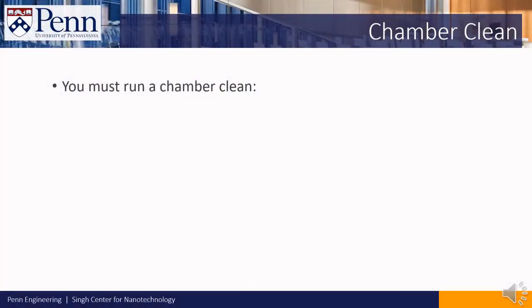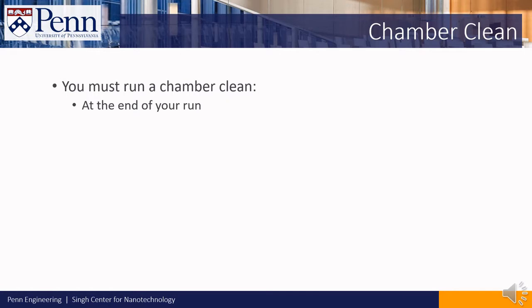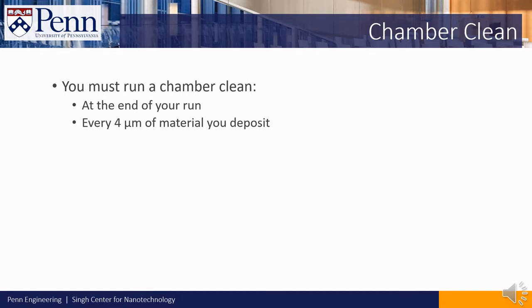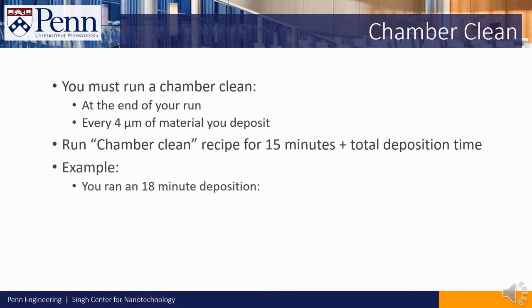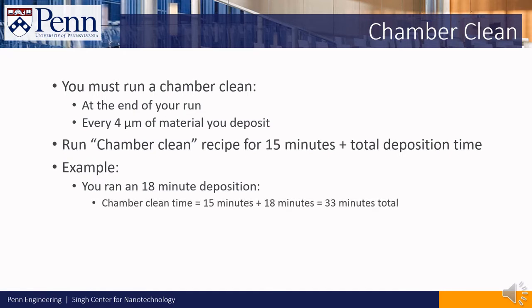Here's the rule in running the chamber clean. You must run a chamber clean at the end of your run and or every 4 microns of material you deposit. When you do run it, run it for 15 minutes plus the total deposition time that you used among all of your samples. For example, suppose you ran an 18 minute deposition on a wafer. The clean should take 15 minutes plus 18 minutes for a total of 33 minutes.